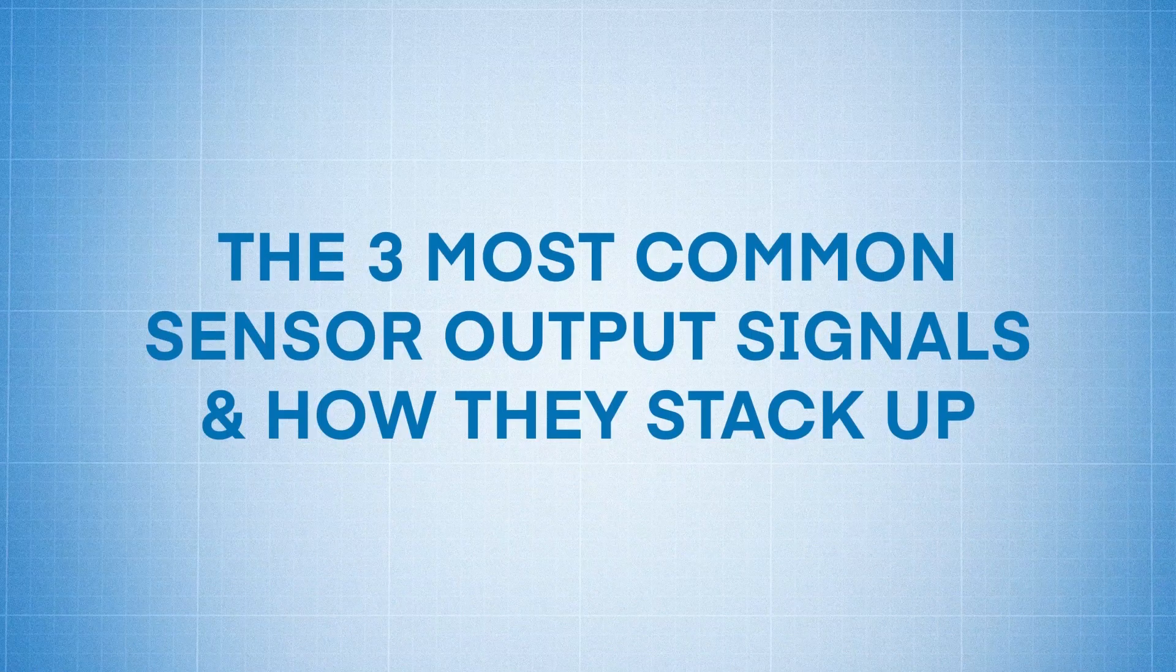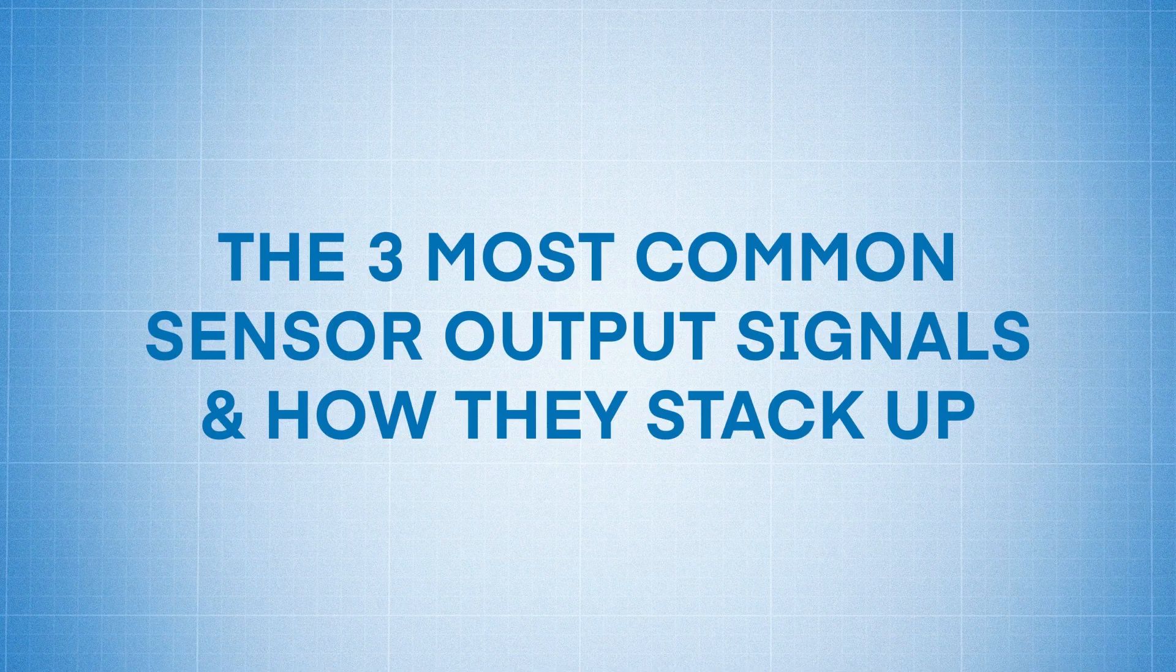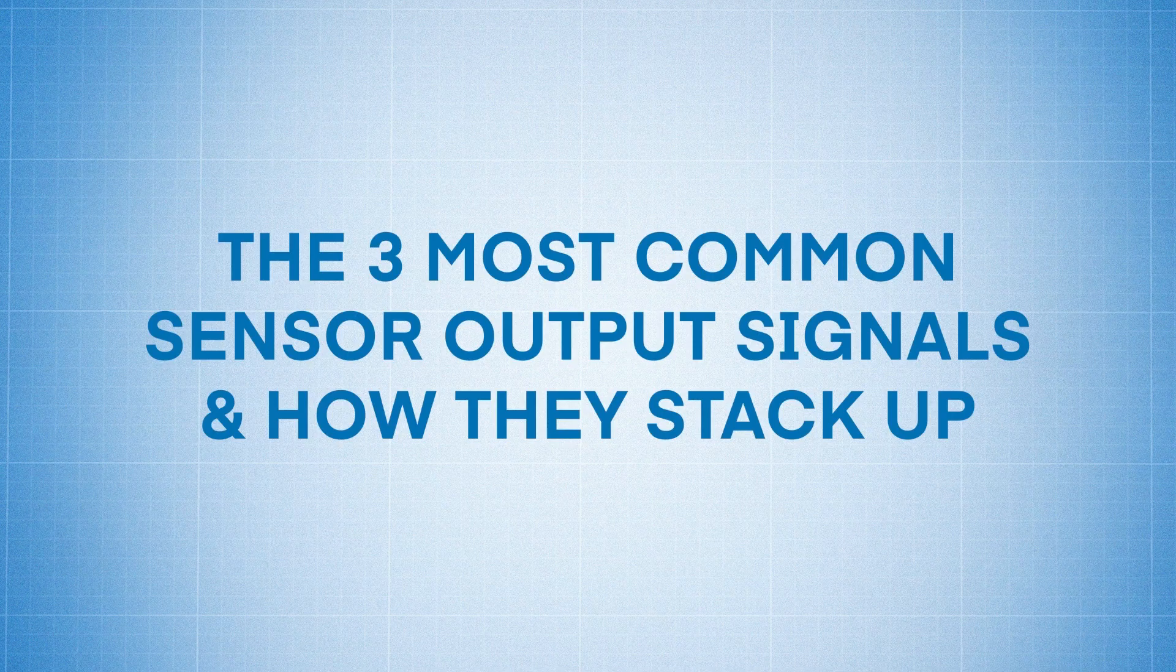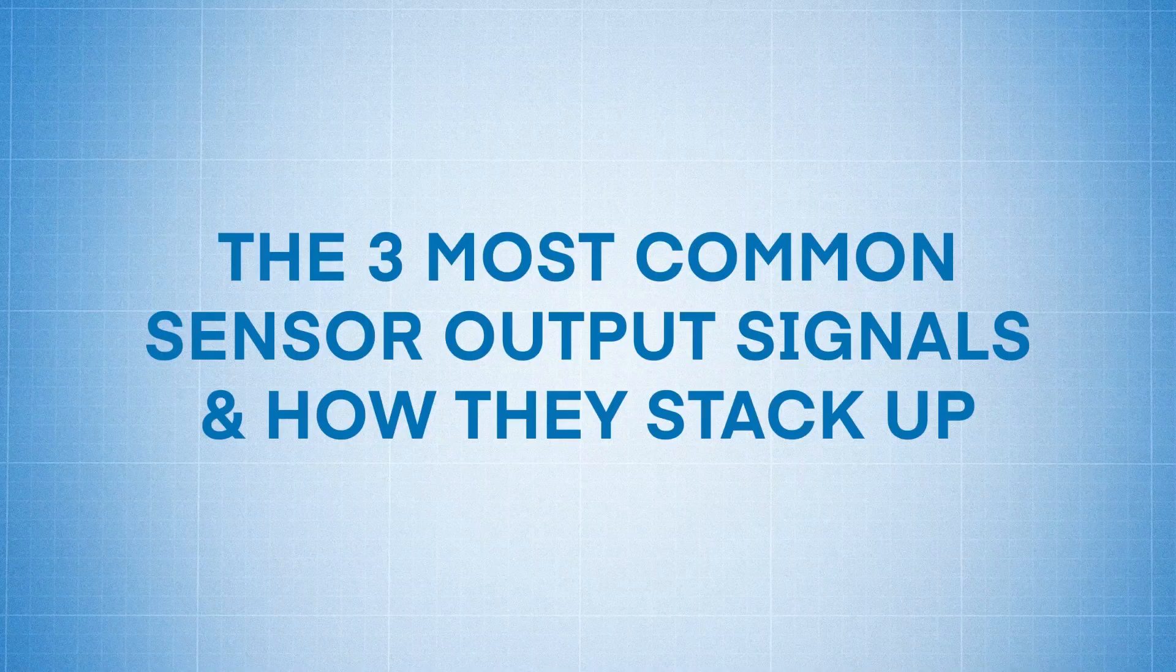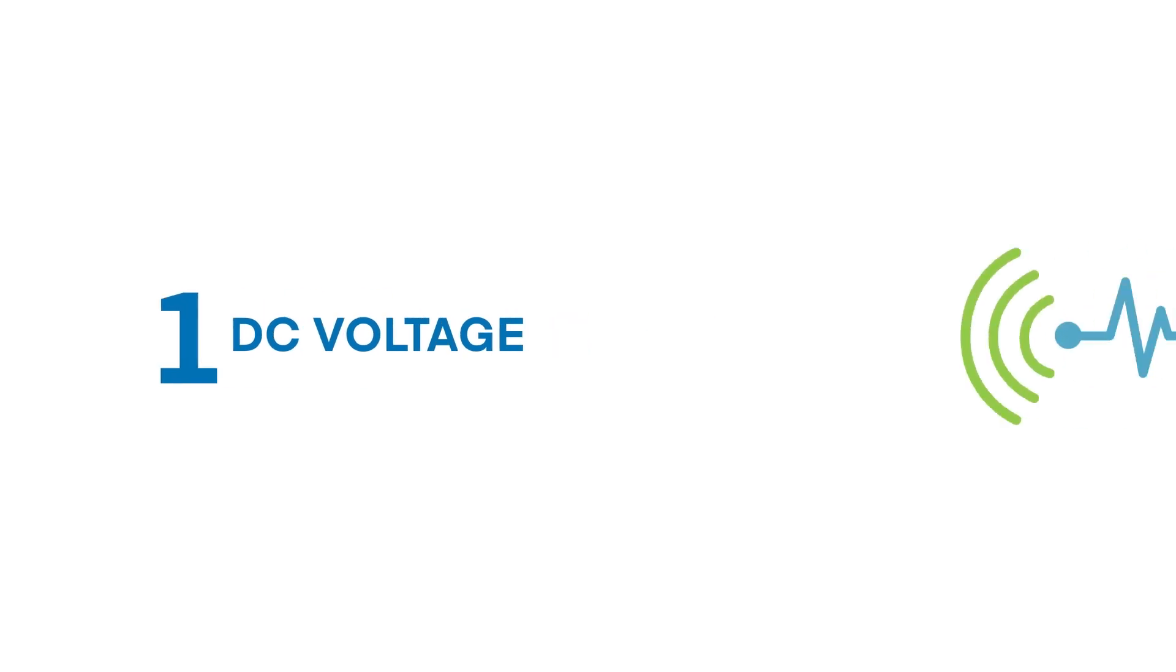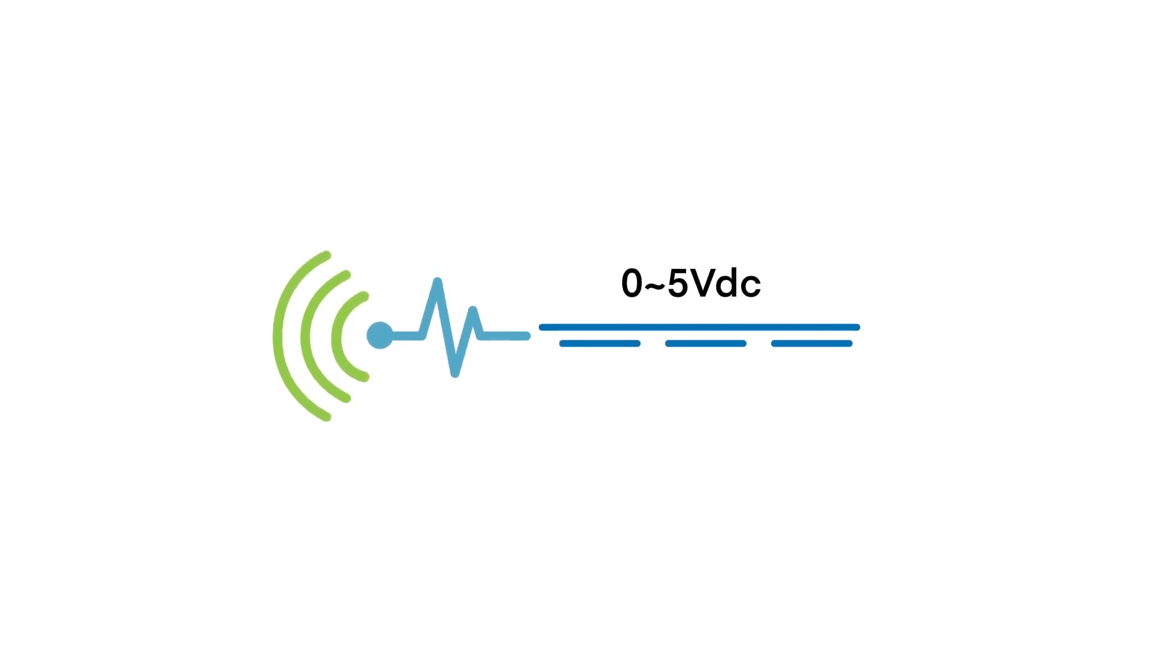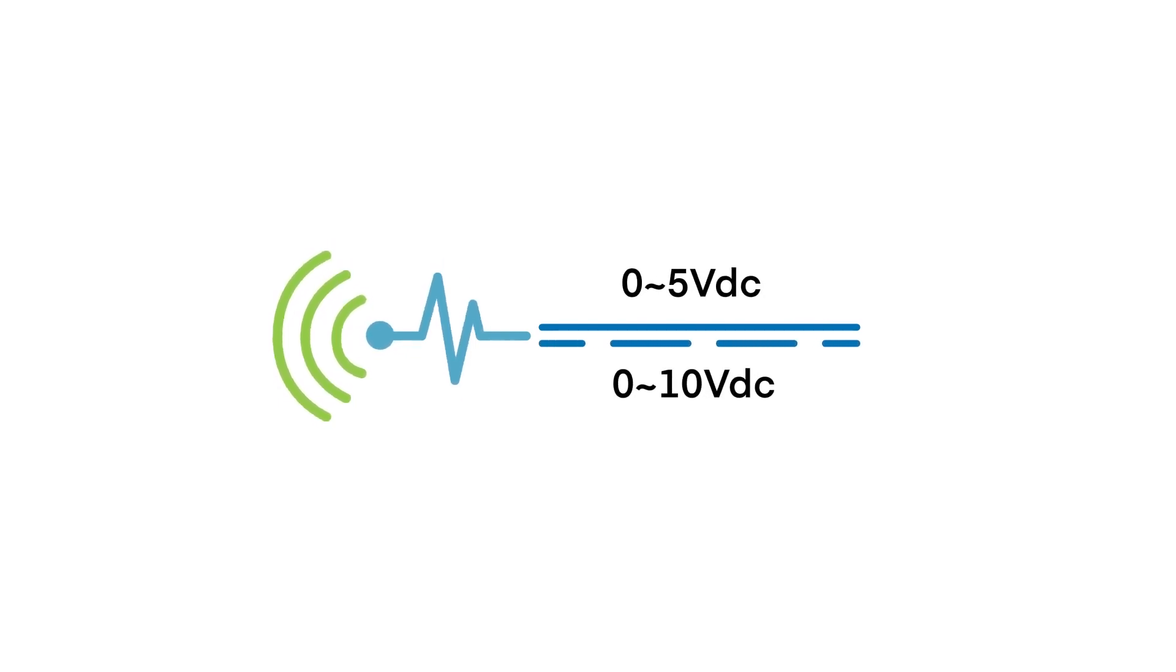Here are the three most widely used sensor output signals and how they stack up. First we'll look at DC voltage. DC voltage output sensors use analog voltage to transmit measurements, with the most common voltage ranges being 0 to 5 volts DC and 0 to 10 volts DC.